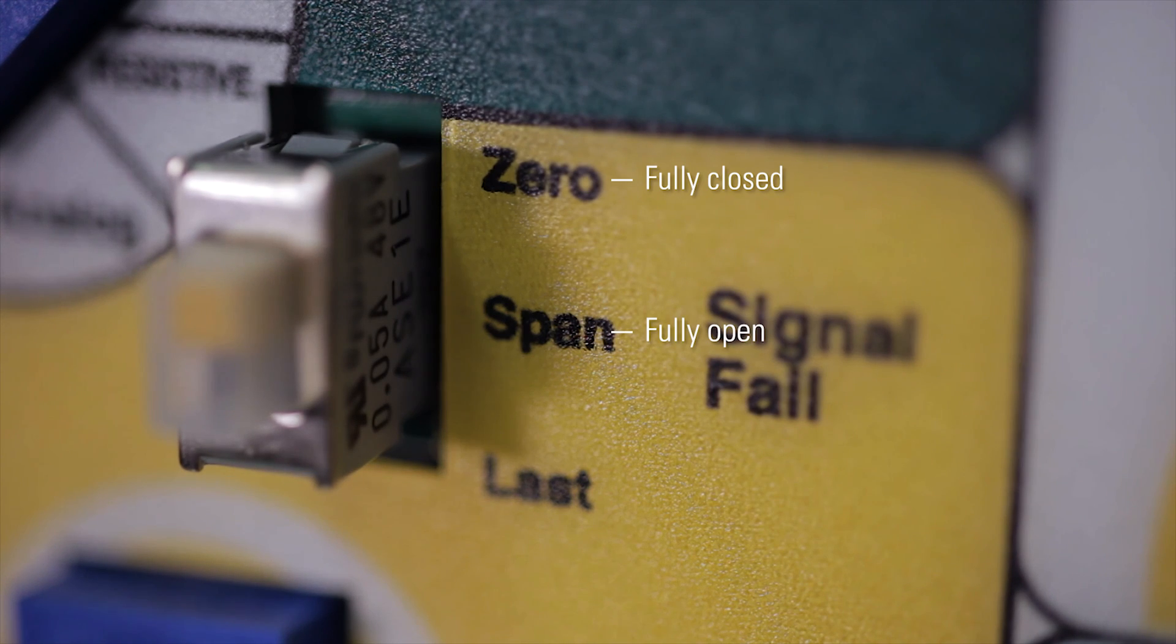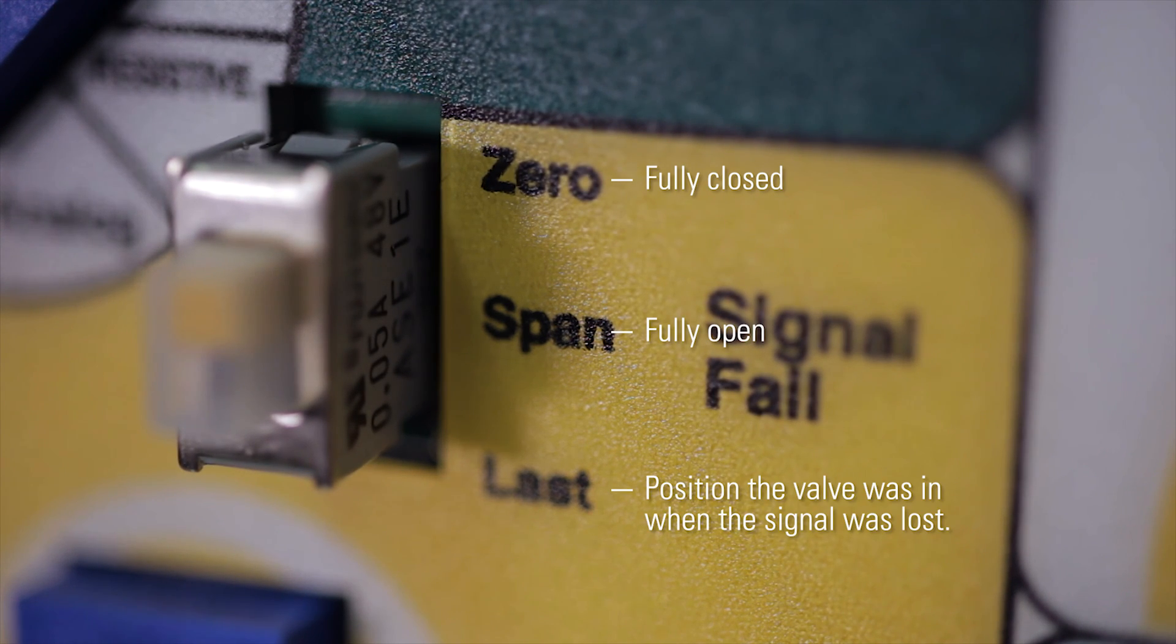If control signal to the actuator is lost but external power is still applied, the signal fail position selector switch provides options for the actuator. Zero, span or last which is the position the valve was in when the signal was lost.